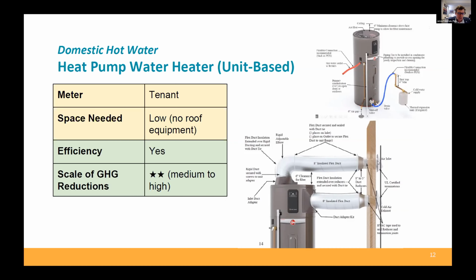One thing we've done to apply these is use the corridor, typically in smaller multifamily projects. We have applications with 55-plus occupancy where we have a single water heater serving three apartments. So you wouldn't have individual metering, but it's been a plausible solution. We tried it, the building was built, we received no negative feedback, so we've done it on a few additional projects, but it has its limitations.